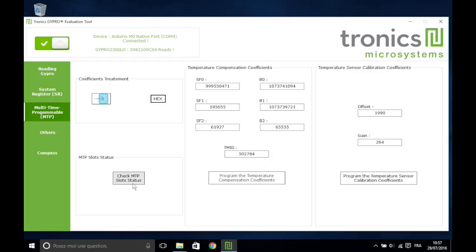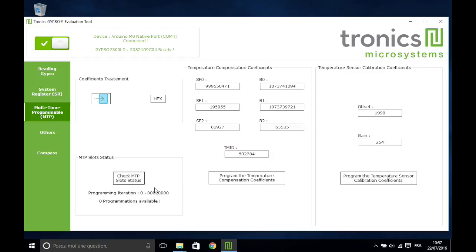For angular rate temperature compensation coefficients, you only have 8 programming slots. You need to click on the Check MTP Slot Status button before clicking on the Program button.